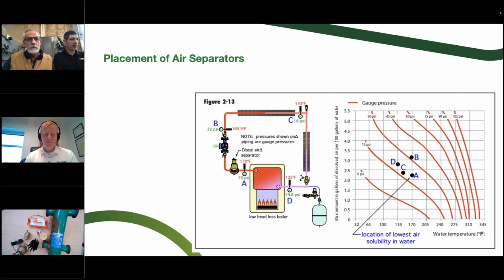If we were to put that air separator after the circulator, as was mentioned, can you put it after the circulator? You can. One of the issues is that you've really boosted the pressure there. So now we're up to 32 PSI, and basically we're forcing those little molecules of gas back into solution, and we won't be able to vent them as well. If we would have put the air separator just before the circulator, we're going to be at a lower solubility, so more of the molecules of gas are going to come out of solution, and we'll be able to vent them.